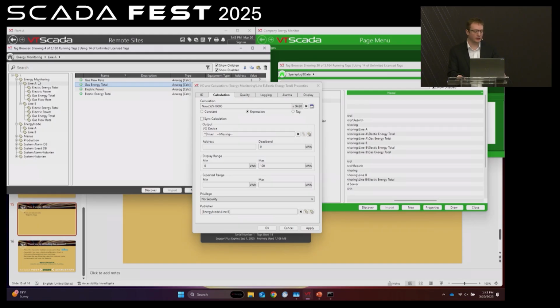Yeah, you can publish to yourself, application to application. You just need two separate port tags pointing at the broker. Don't use the same port tag, you will hang yourself. I learned that building this demo. Each connection to a broker needs its own separate port tag. It's a very easy thing to accidentally link two publishers or two drivers to the same port tag and wonder why nothing works. It's just the nature of how the receiver works and the driver, that you need individual port tags.